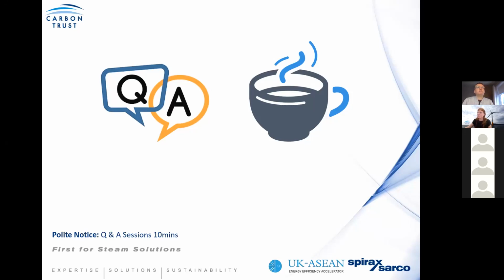Great. Now moving on to steam separators. Does the steam separator need frequent service? And where is the best place to install a separator? Do we need one at the boiler and the steam user point? So there are 3 best locations. We mentioned the boiler.